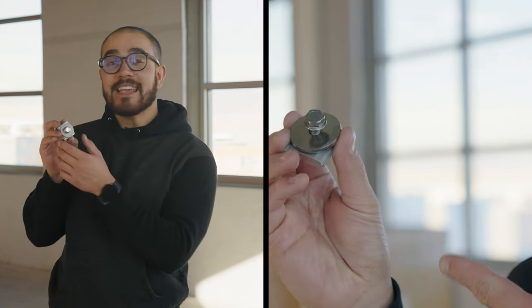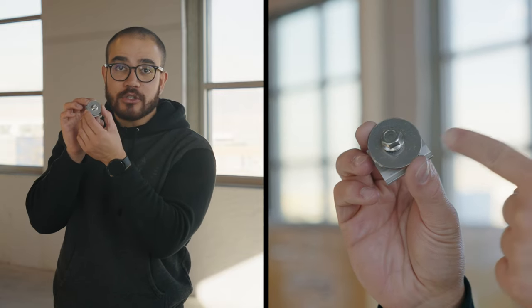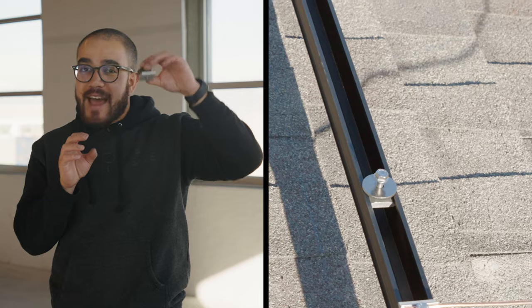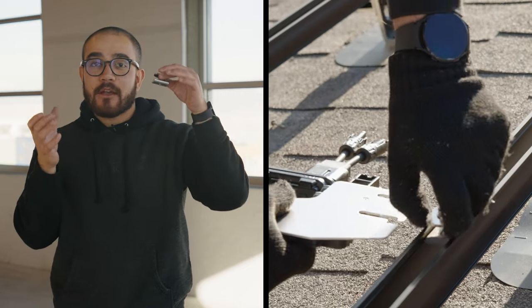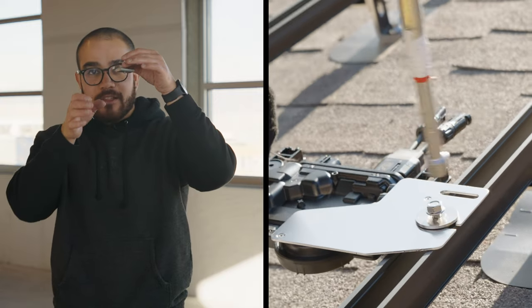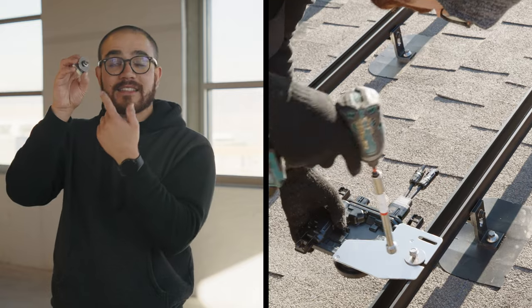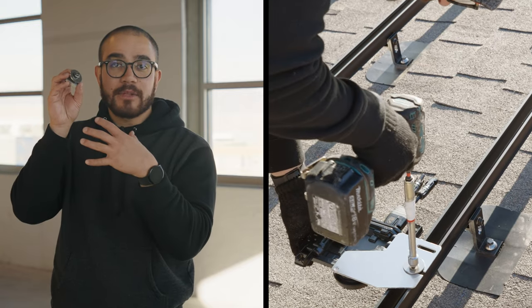This is what's known as an MLPE. Now it looks a lot like the ground lug, but don't let it fool you. One of the key differences is this humongous circular washer. What you do is you fasten this into the SnapNrack railing. You take your micro-inverter, which has a hook, and you put it right underneath this washer. Once it's secure, you just fasten this bolt down and it holds everything in place.